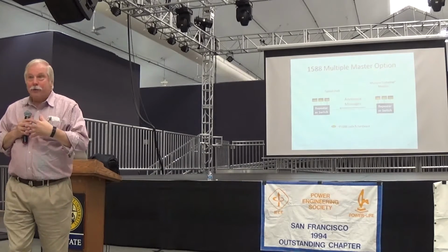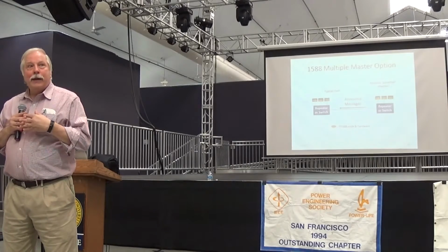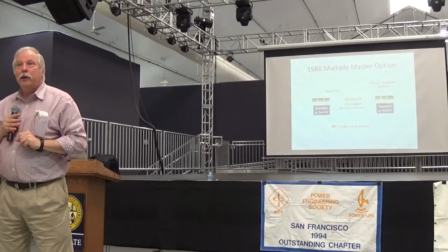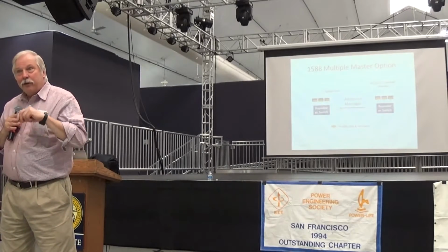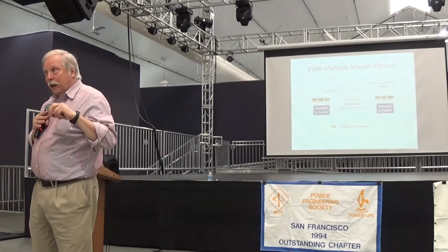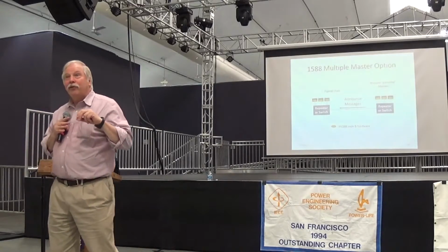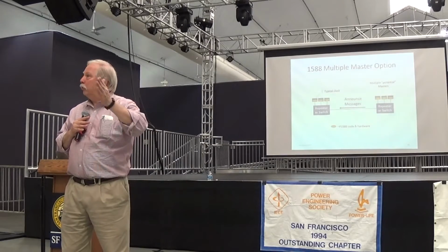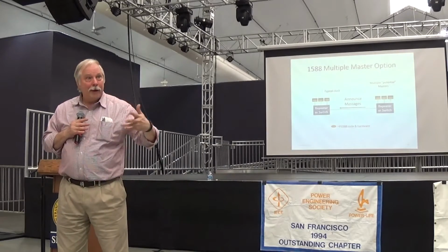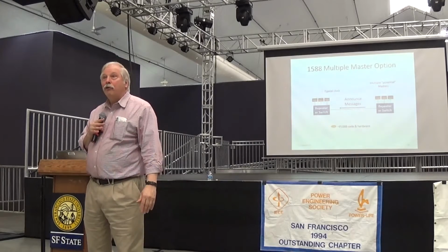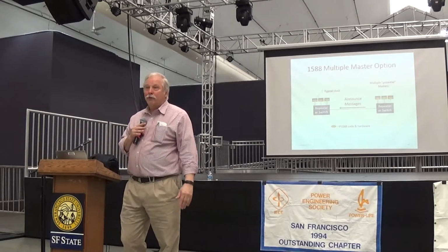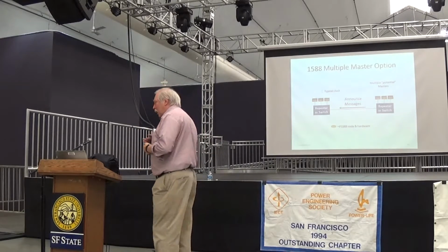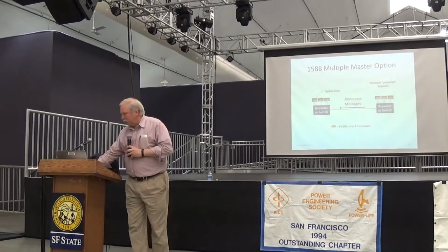With 1588, I'm on an Ethernet network. I can now have multiple grandmaster clocks in my substation. And even today, an IED can dynamically switch from grandmaster number 1 to grandmaster number 2 to grandmaster number 3, or as many grandmasters as you wish in a substation. So we now have a much higher availability of time sync in a substation.